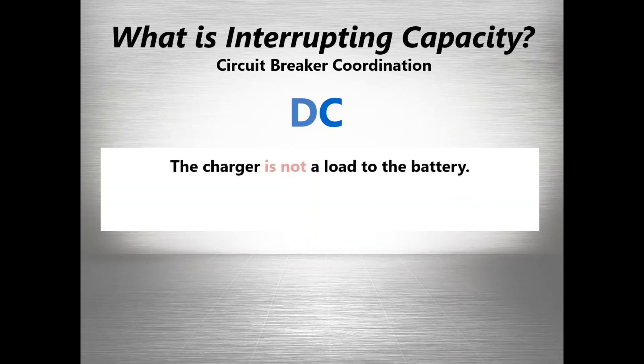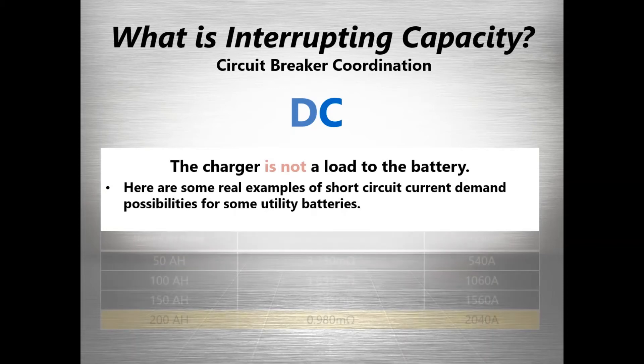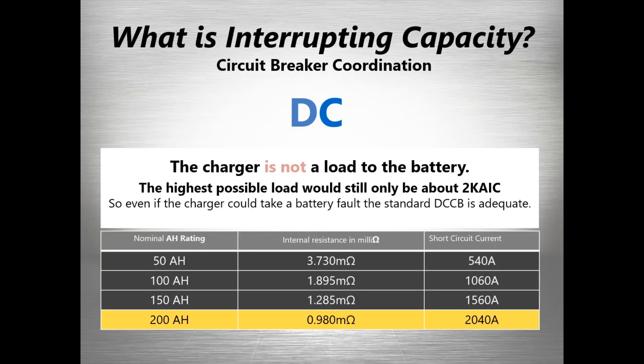If we consider what the interrupting capacity should be, a simple way is to take the battery's nominal ampere-hour rating and multiply it by 10. If you want to do it like an engineer, you look at the internal resistance of the battery — using typical internal resistances in milli-ohms — and calculate that it also comes out to about 10 times the ampere-hour rating. So even the highest possible load would only require about a 2 kAIC breaker, and generally the minimum breakers are 5k. You'd have to get up to over 500 ampere-hours before you'd even consider going to a higher breaker — using a theory that doesn't actually hold water.